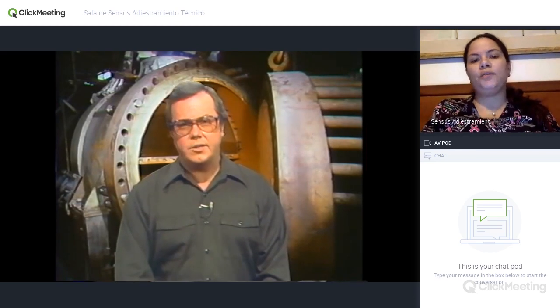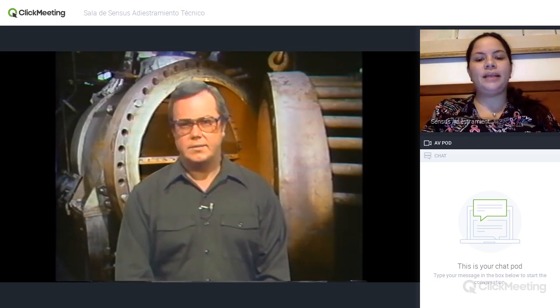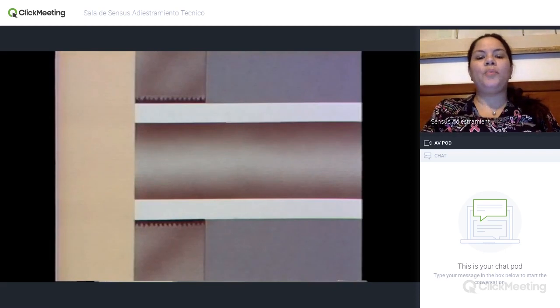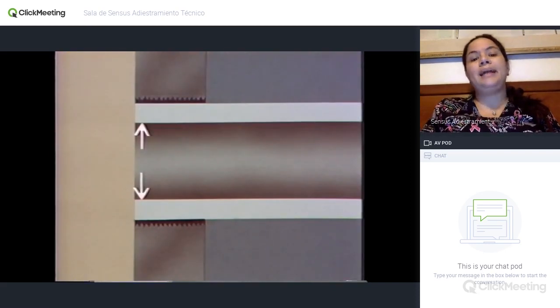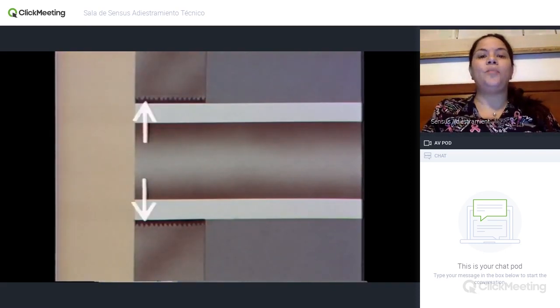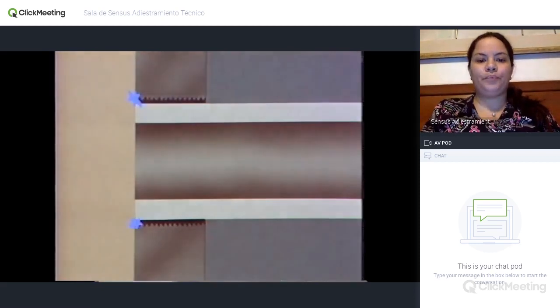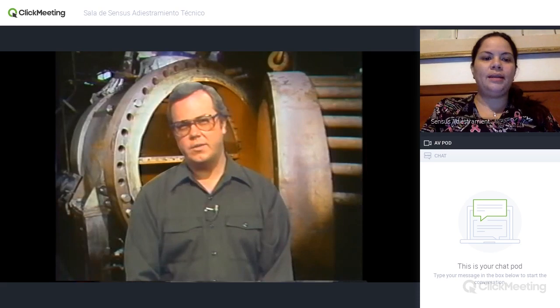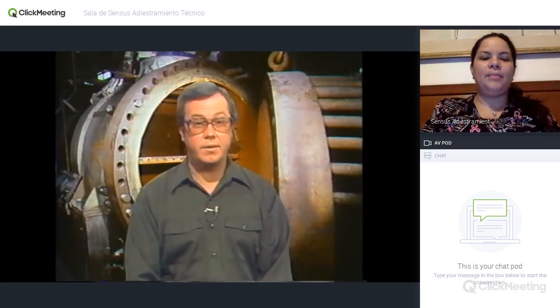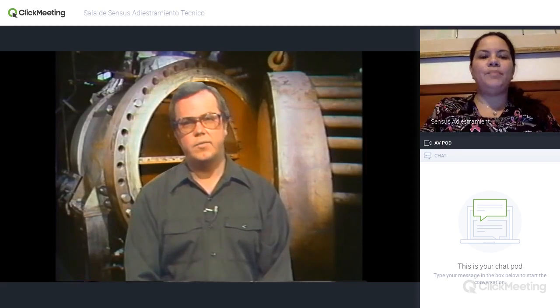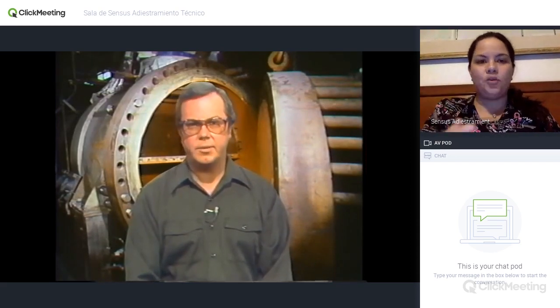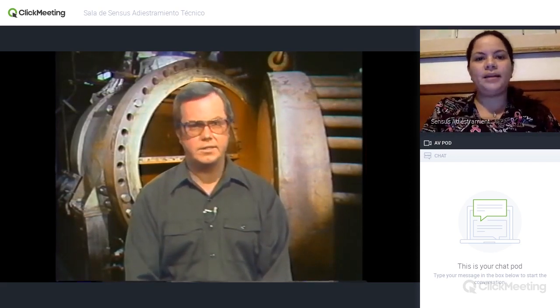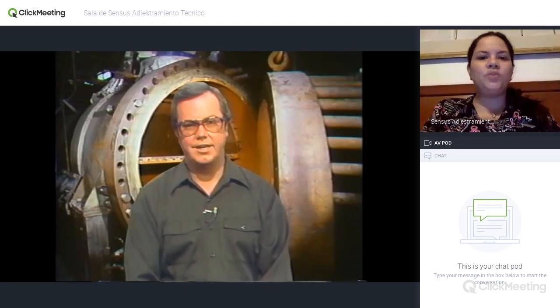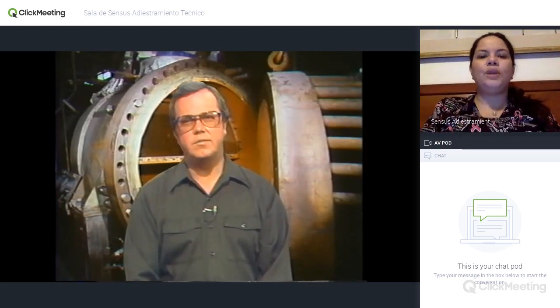Tubes are usually set into tube sheets in one of two ways. One method is by rolling, which is a way of expanding the ends of the tubes into corrugated openings in the tube sheet. The other method is to weld the tubes into the tube sheet openings. Whichever way the tubes are set into the tube sheet, any that have to be replaced must be cut away very carefully. After removing the old tube, the new tube is set into place and fixed to the tube sheet the same way as the original tube. We'll be studying these things in more detail further on.